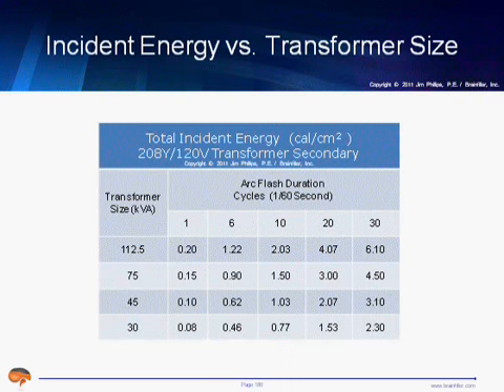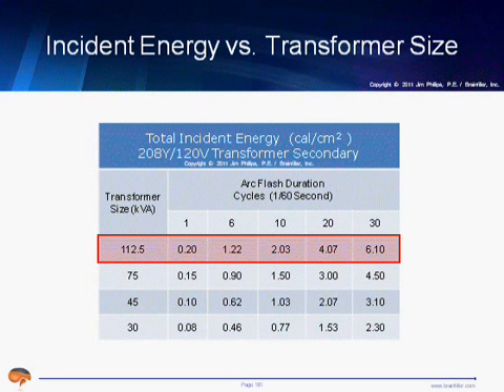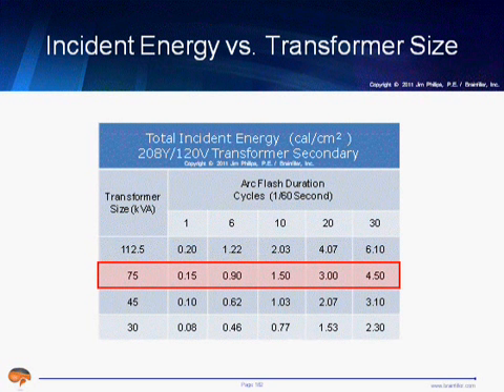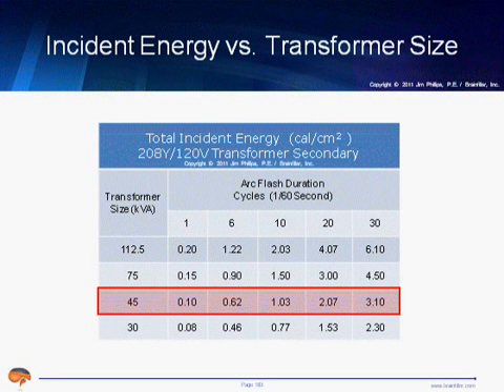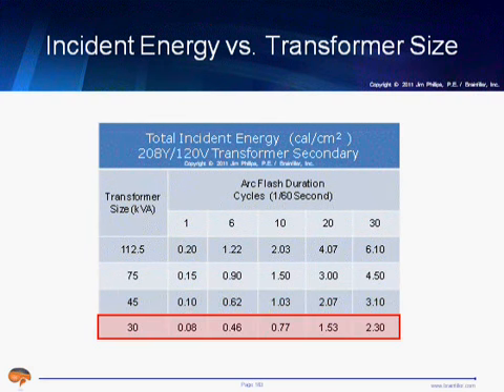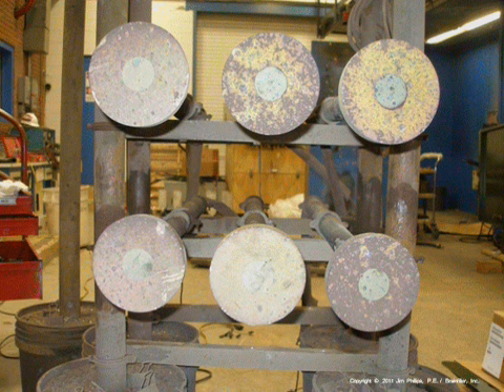I ran through a few example calculations, just looking at short circuit currents from transformer size and from duration. With a 112.5 kVA transformer and a one cycle duration, you have a very minimal amount of calculated incident energy. You need to go up to 6 cycles before you get into the 1.2 calories. With the 75 kVA, it drops. A lower, smaller transformer means less short circuit current. With a 45 kVA transformer, it becomes even lower. So the big issue right now, and these are things being investigated, is what does it take to sustain an arc flash? Do they self-extinguish? The answer is not there yet, but there's a lot of really good work going into it.